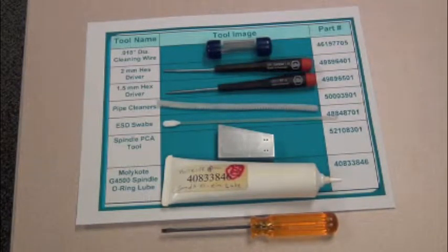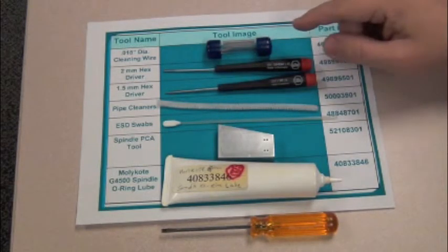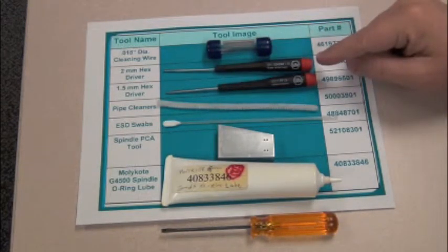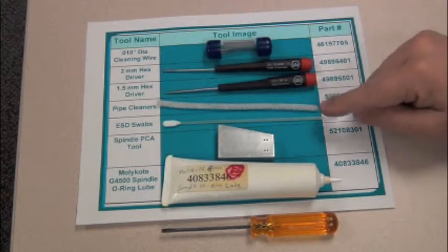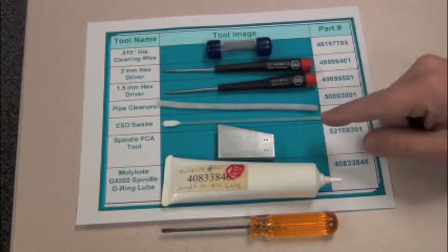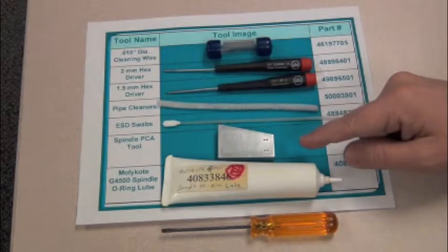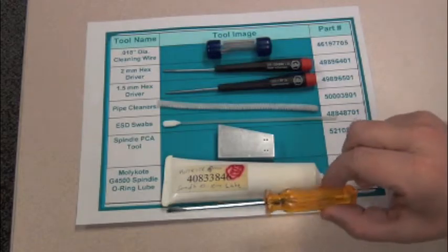These are the tools required for the spindle performance upgrade. You'll need some .018 inch diameter cleaning wire, one 2 millimeter hex driver, one 1.5 millimeter hex driver, some pipe cleaners, some ESD swabs, spindle PCA removal tool, Molykote G4500 spindle o-ring lube, and a small flathead screwdriver.